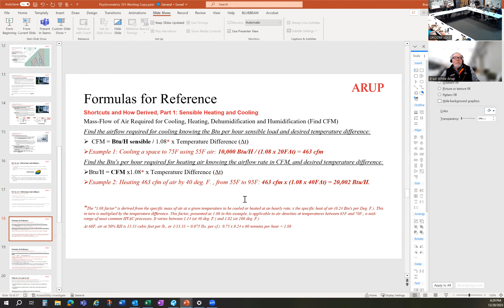I wanted to explain in more detail what those numbers are based upon. It has to do with the pounds of air you're moving, the specific heat of air, which is 0.24 BTUs per pound to change it 1 degree, and 60 minutes per hour since we deal with cubic feet per minute but talk about heat transfer on an hourly basis. This explains how the 1.08 factor is derived and where it comes from.